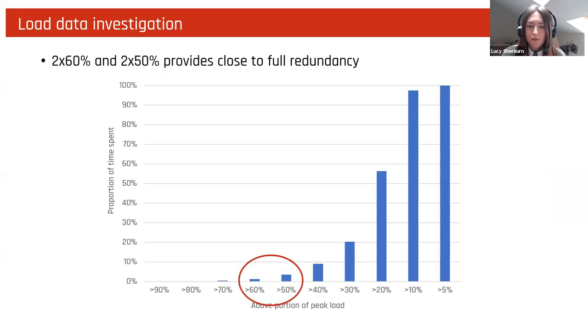Next slide, please. We also looked at the proportion of year spent above a percentage of peak load. You can see that 55% of the year was spent above 20% of peak load, but that also shows 45% of the year was spent below that. So a large portion was again spent at low load. But what's interesting is that when you have a plant sized at either 50% or 60%, there's very, very little amount of time spent above that. So using those size plates almost provides you close to full redundancy.